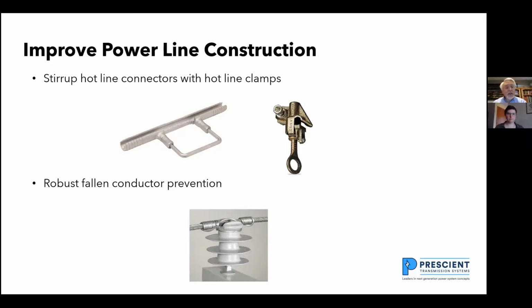So a thing we can do is to put stirrups on, so that what you do is you actually swage a stirrup on the power line and then put the hot line clamp on the stirrup. If the connection becomes loose and the hot line clamp falls to the ground, it's not a power source anymore, and you're not going to ignite dry vegetation.